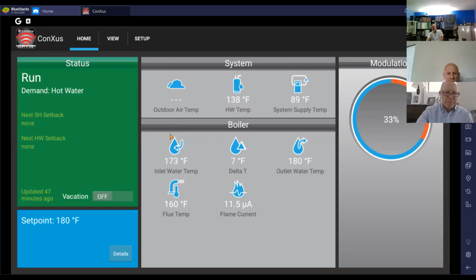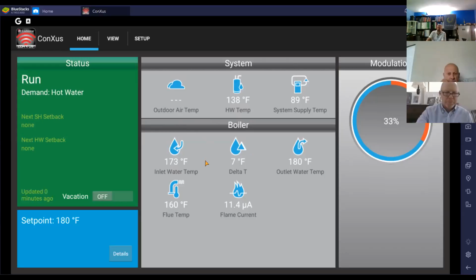Now this boiler is a bank of 3, piped in primary-secondary, and it uses a condenser water loop in the summertime to do heating and cooling. That's why the system supply temperature is at 89 degrees. The tank right now is at 138 degrees for domestic hot water. Here's where the boiler is operating - so that gives you what's happening right now.